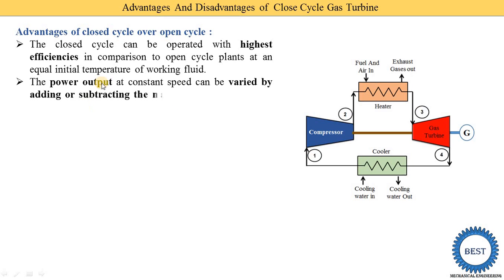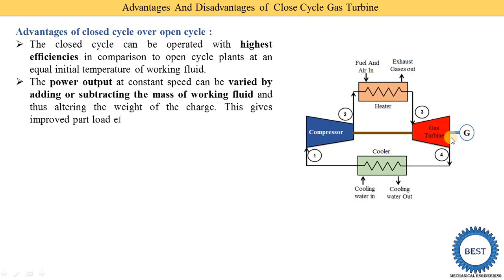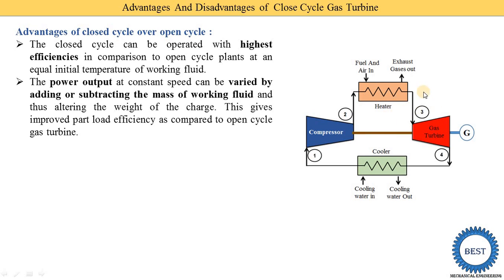The power output at constant speed can be varied by adding or subtracting the mass of working fluid, thus altering the weight of the charge. This gives improved part load efficiency compared to the open cycle gas turbine. Some provision is made so that working fluid can be added or removed — this refers to the working fluid circulating through the components, not the fuel being burned.